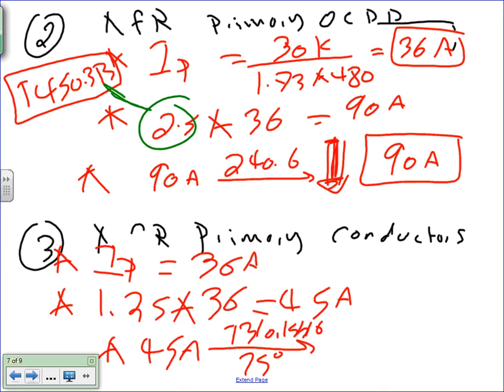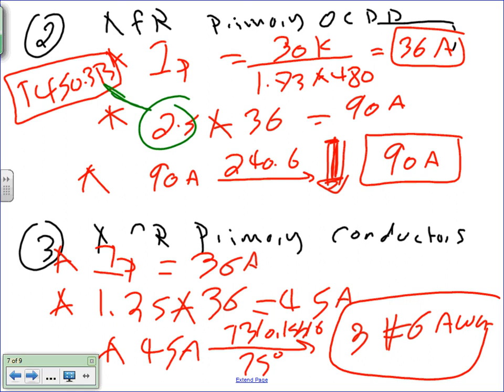Yes. Because if you go to 450.3(B), there's no note number one. Remember we talked about note number one on the table? There's no note number one that tells you to go down on the primary. On the secondary, it does. Not on the primary. Okay, so what's the conductor? Chris, I have 3 number 6, right? 3 number 6 AWG. Now the question is, why not 4? We're bringing in a delta transformer, guys. Most likely it's going to be delta on the primary. 3 conductors. I don't need a neutral on the primary side.